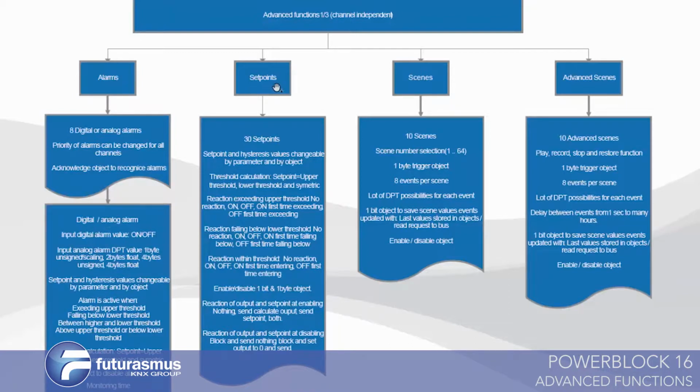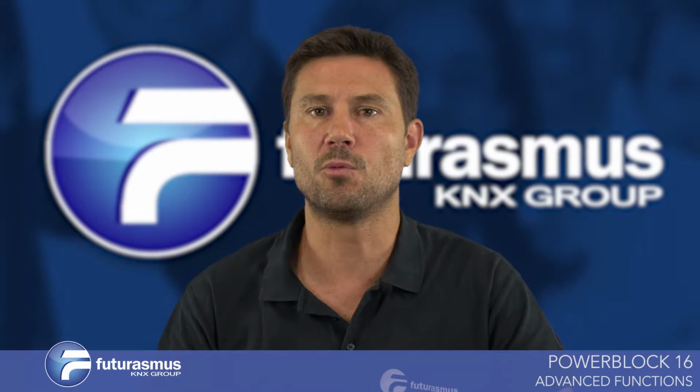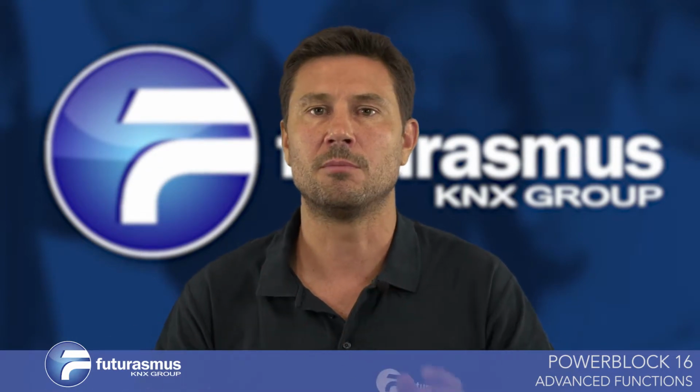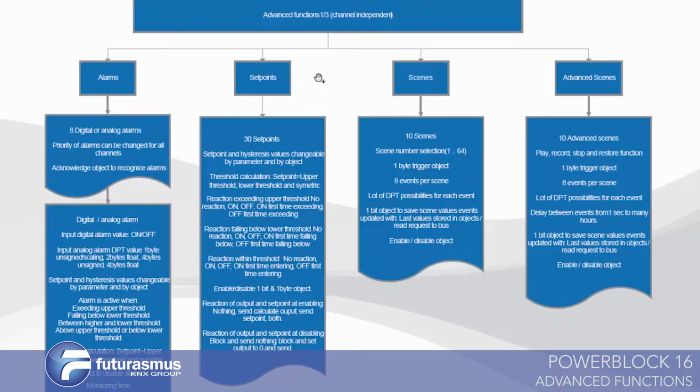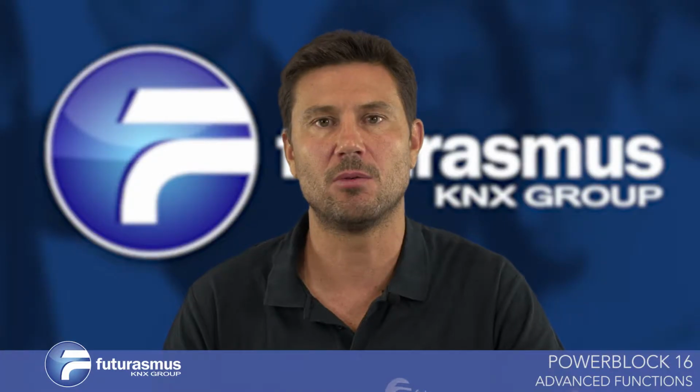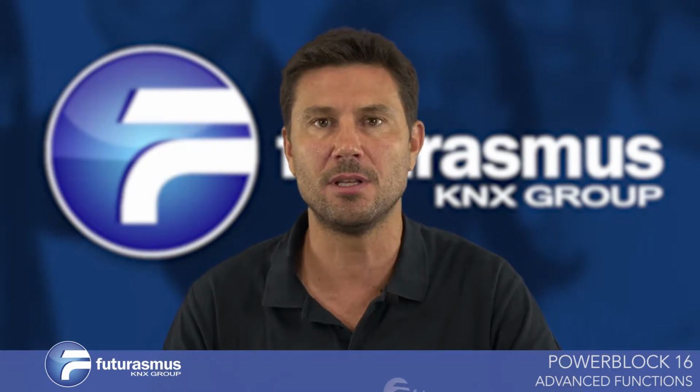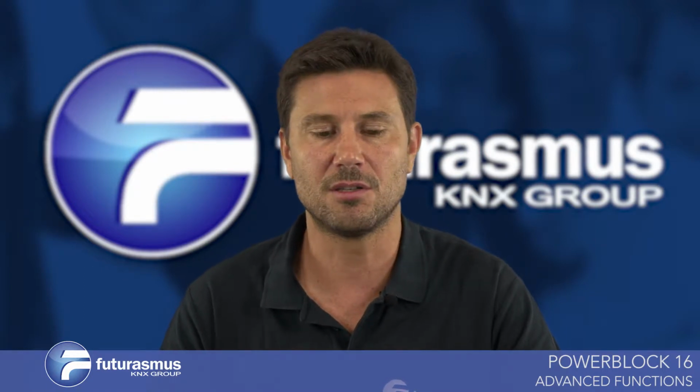Then the set points are very interesting. It's like a 2-point regulator, like a threshold which can be used additionally to the alarms. We have the output, the channel will be blocked. Okay, in the set points you can decide what should happen. You can send the output of the set point to an alarm, to a disable function of the output, or just to trigger an event in the device.